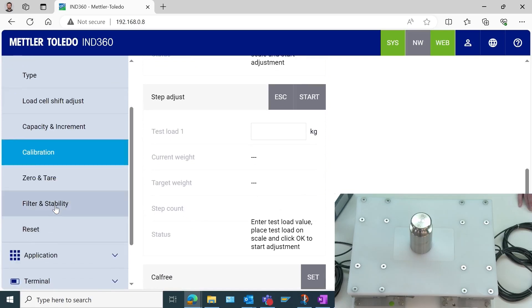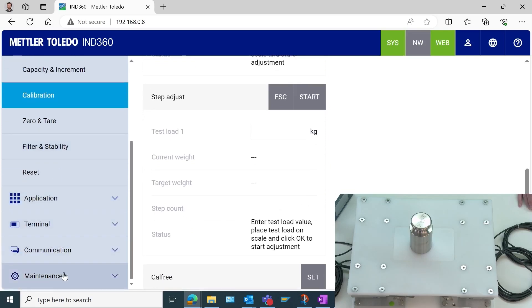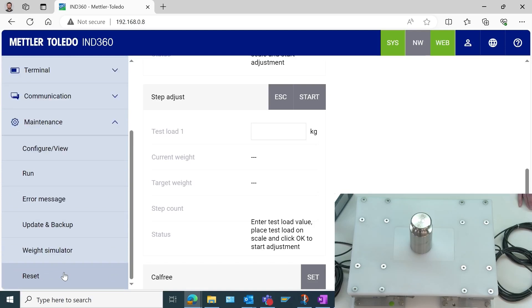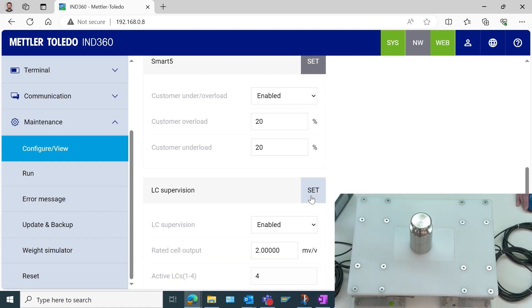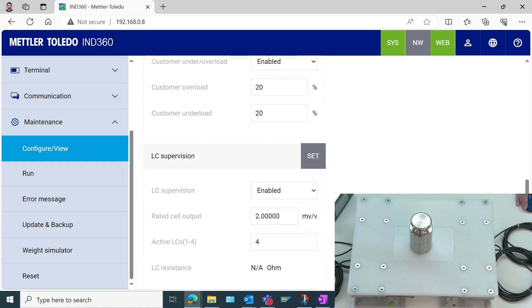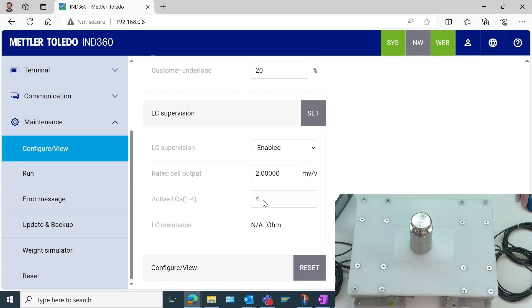Now the final thing we're going to do here is come down to maintenance. And I want to make sure that I can detect if one of my load cells were to become disconnected. So I'm going to go to configure and view. And then this feature called load cell supervision here down at the bottom, I want to enable this. And I need to put in the average rated cell output of the four load cells. These all happen to be 2 mV per volt load cells. So I'm okay sticking with this value. It knows that there are four load cells connected.